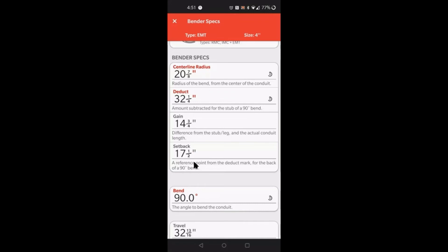From that seventeen and a half, from that deduct mark, let's just say you wanted a kick from the back of the 90, 20 inches. What you simply do is from where you just put your deduct mark, where you just measured and laid out your 90, from that last mark where you're going to actually place your bender and your conduit in the bender and bend, from that mark you measure 20 inches because you want that kick 20 inches away from the back of the 90, plus the setback. So you would measure 37 and a half inches, and that mark right there where you mark it, that's where you're going to place your conduit so that you can kick it and it'll land 20 inches away from the back of the 90.